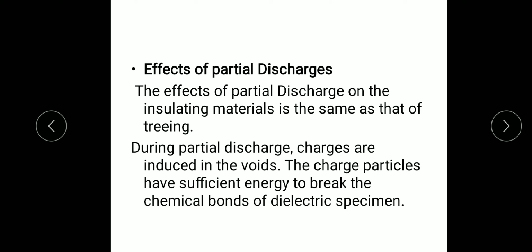Next is chemical degradation. Chemical degradation also takes place in this, and as a result the thickness of the insulation will be reduced. During partial discharge, charges are induced in the voids. The charged particles have sufficient energy to break the chemical bonds of the dielectric specimen. This is about partial discharge, and this is the end of the topic, breakdown in solid dielectric material or solid insulating material.